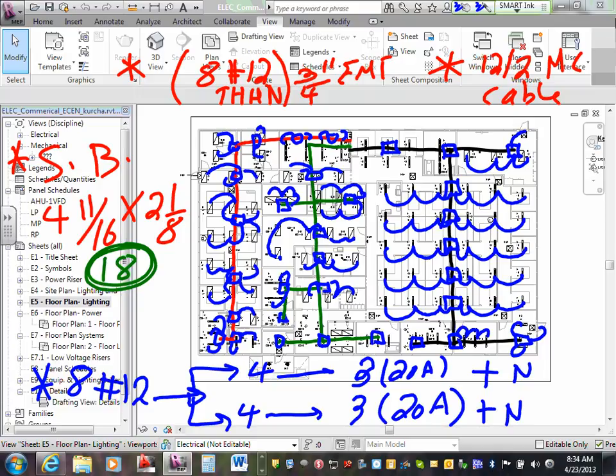So basically, if you want to know how to do it, take how many lighting circuits you have and divide it. If you have 8 number 12 conductors, that gives you 4 conductors each. Each 4 conductors can give you 3 circuits, 20 amp, plus a neutral, right? 3 phases and a shared neutral. That's how I build my system. So the 8 number 12s will be divided into 4-wire multi-wire branch circuits. Brian, my friend, multi-wire branch circuit. This multi-wire branch circuit can give me 3 circuits, 20 amp for all my lights, plus the neutral conductor. So I have 6 circuits.